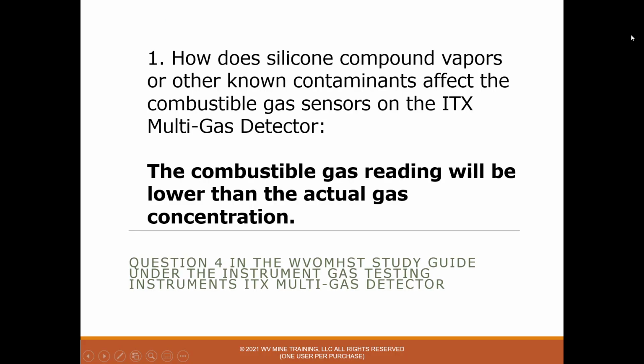So question 1, how do silicone compound vapors or other known contaminants affect the combustible gas sensor on the ITX multi-gas detector? And the answer is the combustible gas reading will be lower than the actual gas concentration. Somebody says, well, what's silicone compound vapors? I've tried to research that and really can't come up with a good answer. But just imagine anything out of the ordinary that this detector would sense. Maybe even bolter glue, the resin glue that you use on a roof bolter. Maybe it could even, I'm going to just say, smell that, and it would adversely affect the readings.